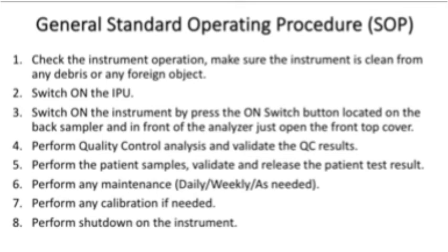Fourthly, perform quality control analysis and validate the QC results. Fifthly, perform the patient samples, validate and release the patient test results. Sixthly, perform any maintenance, which is daily, weekly, or as needed. Number 7, perform any calibration if needed. And lastly, perform shutdown on the instrument.